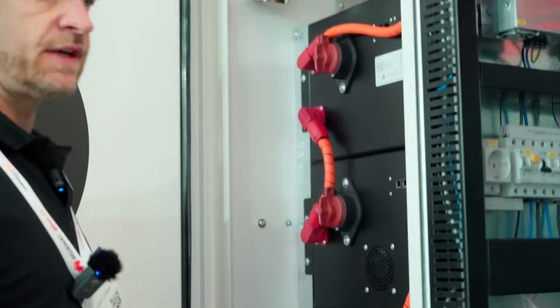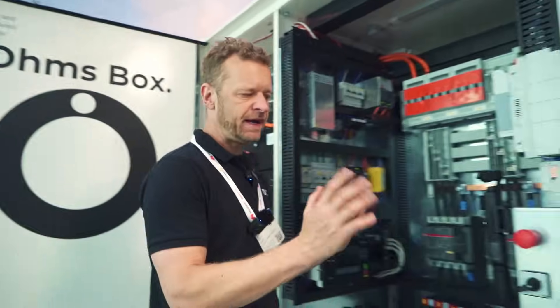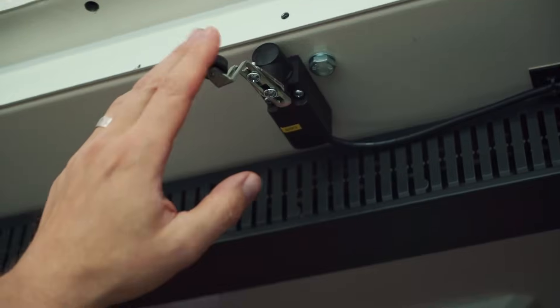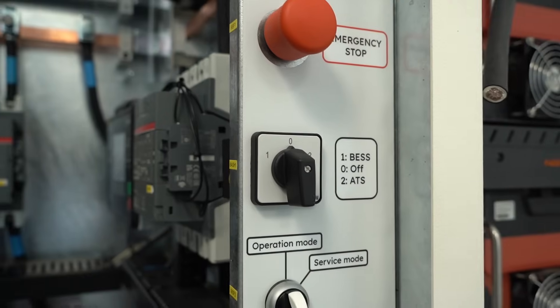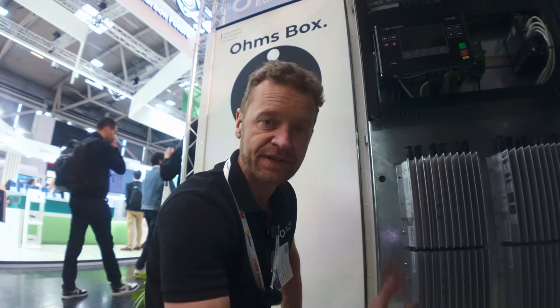Once disconnected, you check your voltage — 76 volts. That will not kill you; it's almost impossible. Now you have a system that is safe to work on, with no dangerous DC situation. When we open the door, this switch — also an earlier model; the next version will have a proximity sensor — has effectively turned off the system. Zero means the system is off, one means BESS mode with all the bells and whistles, and number two is ATS mode, which I'll get to later. That's the point of the system: integrating everything into one box, so you just need one box instead of four or five.